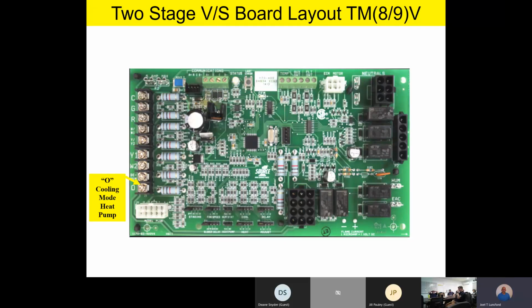Because if you have it on the heat pump position and you don't have a heat pump hooked up outside, it'll throw a flash code that says, hey, I'm getting an O signal, but we don't have a heat pump outside. So just keep that in the back of your brain. It's one of those little things you need to double check when you commission the board, because if you put it in the heat pump position, it's going to be looking for an input on the O terminal, which is the cooling mode for the reversing valve on a heat pump. Any questions or comments on that before we continue?